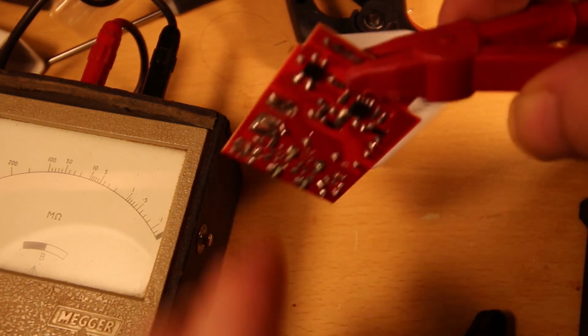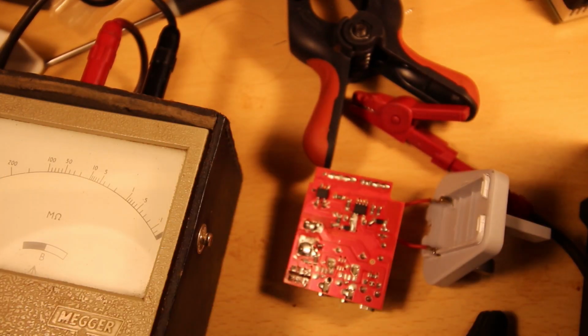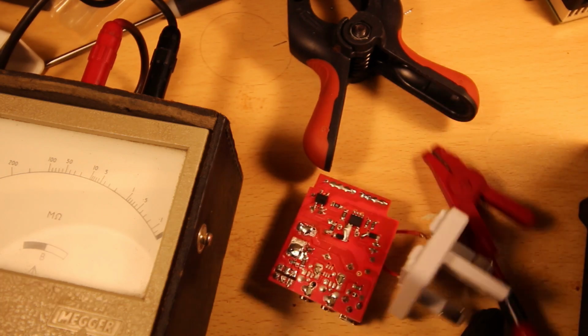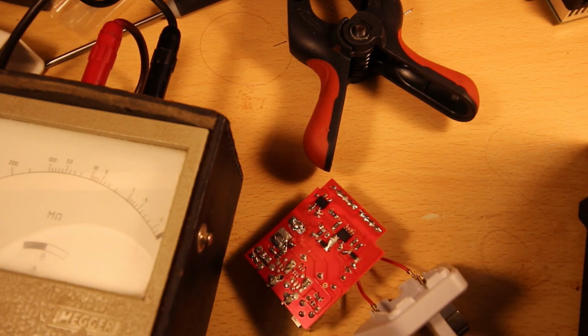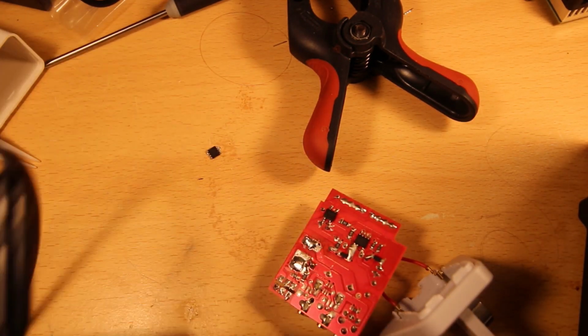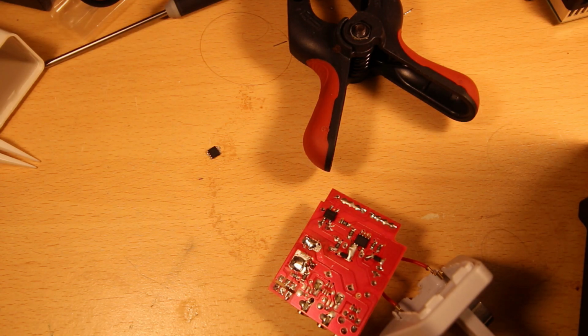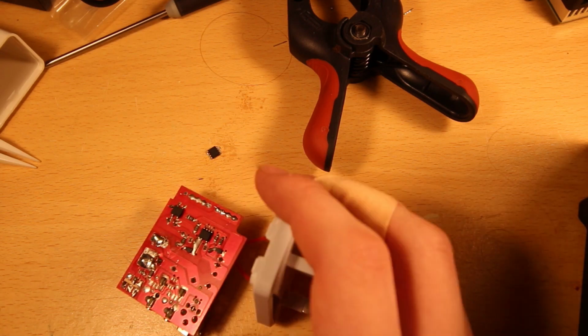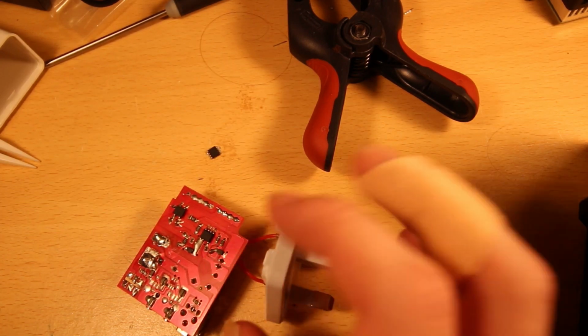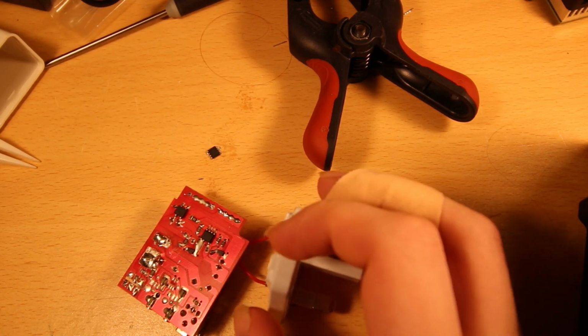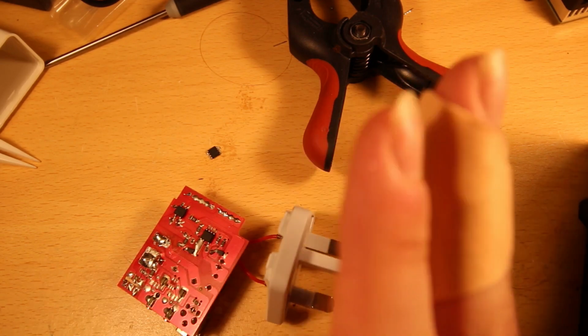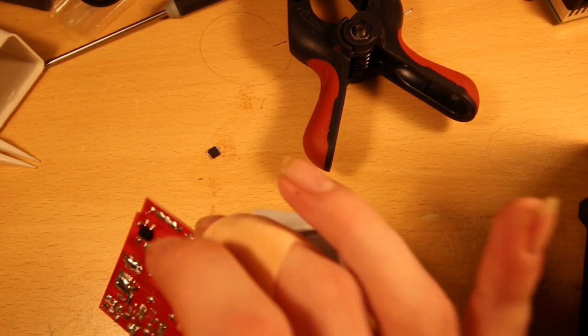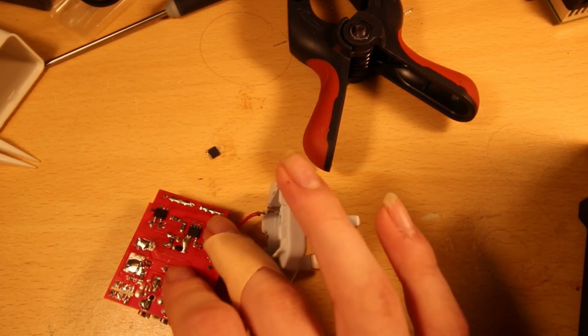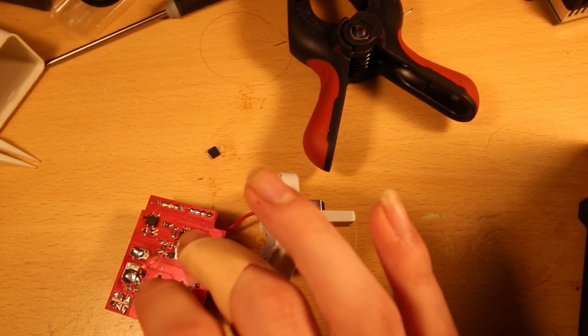That's not massively surprising because it does have a not completely crap looking capacitor in it, and I'd expect the varnish on the wire in the transformer to sustain 1000 volts for a few seconds. As I said, I'm not going to bother with the 10,000 or 11,000 volt test I sometimes do, for reasons I already said. So let's get the transformer out of this and tear it down and see what the isolation is like.